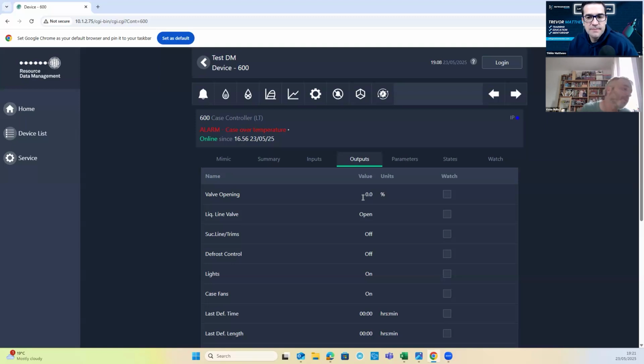Okay. So what you sometimes find, let's say you haven't started a vacuum for whatever reason, or somebody hasn't fitted your transducer and you've got a 0 bar bottom of the range, is the reading will go in and out. 0 on a 0 to 60 bar transducer is right on the edge of detecting a fault. So if you're not sure, if it looks a bit funny, put some standing pressure in it. When you've finished vacuuming it out, just open the suction, let the pressure come up and see what your reading looks like. Compare the reading you get then to what you're getting on the rack or on your gauge, depending on where you got connected, and go from there.